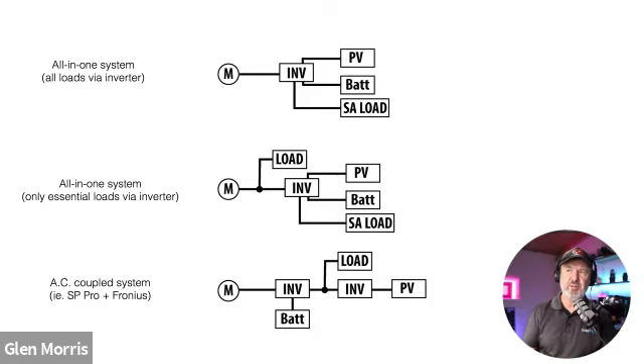Running the whole home off standalone loads is a pretty big ask, because generally homes have energy peaks greater than the inverter can supply. So more normally, the middle option is where only your essential loads are supplied — the things you want to back up if the grid fails. That's the middle line. The bottom line needs a bit more explanation: there are actually two inverters, a battery inverter and a solar inverter, and they work together to supply energy to the loads even when the grid's down.